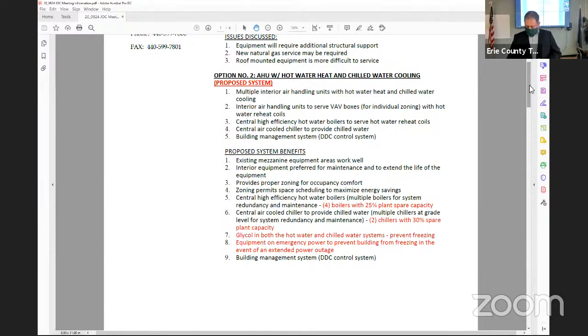Some of the other things I talked about, the glycol, but with interior air handling units, another advantage, we can look at putting some of them on emergency power because we're only dealing with a fan motor. We would already be looking at the hot water plant and hot water pumps on emergency power. That way, if you have an extended outage, you can circulate water through the building. If we get several air handling units on the emergency generator, could serve core areas, could keep the building up and running for several days. Maybe not at optimum temperatures, but certainly enough to keep it from freezing.